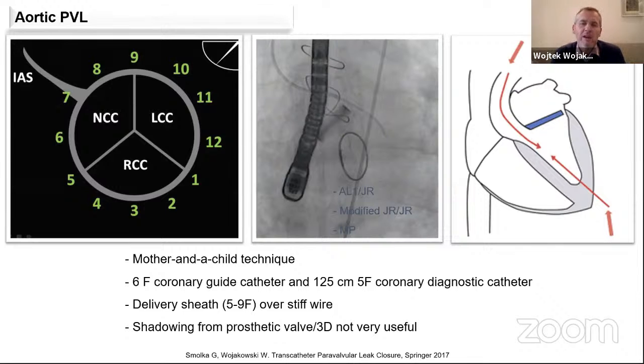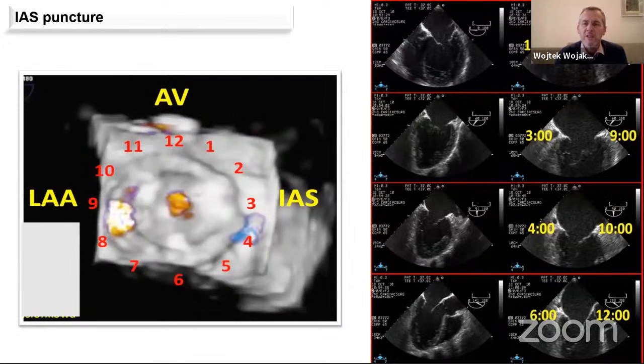For a single plug, you can use the 6 French catheter to deliver the AVP3. And for multiple plugs or for larger plugs, you exchange over the wire, over the 300 or 260 wire, for the vascular sheath, like the Q sheath, which can start at 6 French, and you can use up to 8-9 French if you need, and of course if the track of the PVL permits.